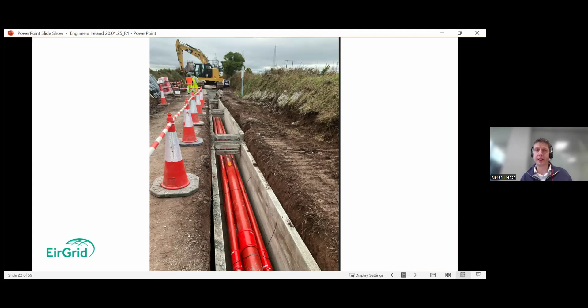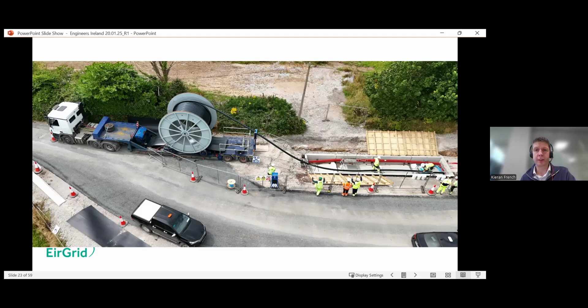This is an image of a joint bay and the cable being pulled into the joint bay, showing how the cable is delivered to the work site and then pulled through in a tensile controlled environment through the joint bay. At this end we've got the drum on the back of the truck on a roller system, and at the other joint bay we'd have a pulley and a winch. Again, careful coordination is needed to manage the tensile stresses on the cable as it's being pulled through the ducted system.